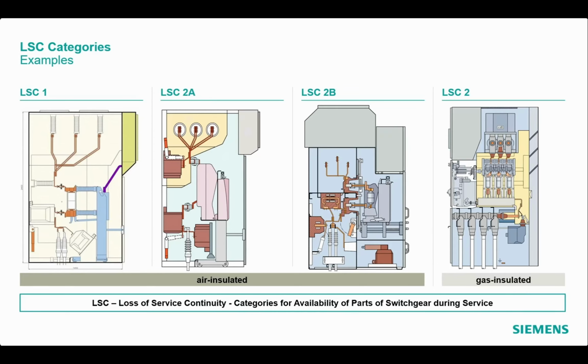The first three are applicable for an air-insulated switchgear, and the last one on the right side for a gas-insulated switchgear. In the first picture on the left side, we see the category LSC1. Here, no service continuity is provided. Opening any accessible compartment requires the entire switchgear to be de-energized.